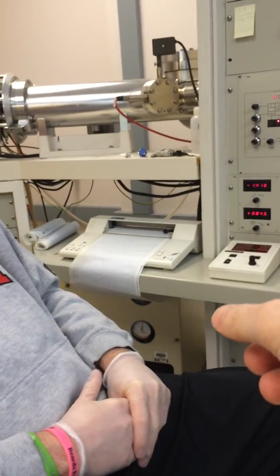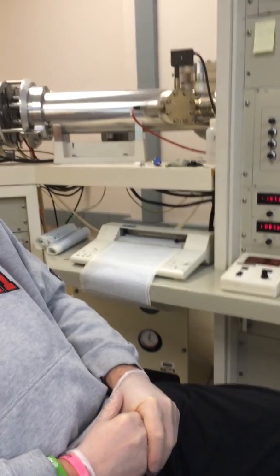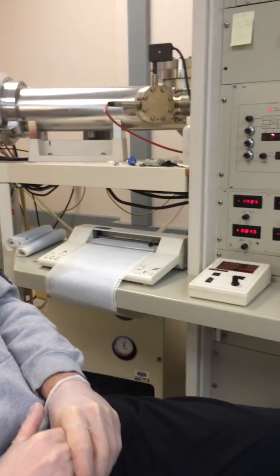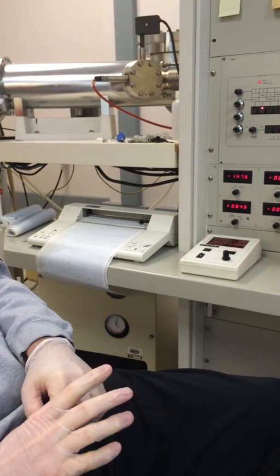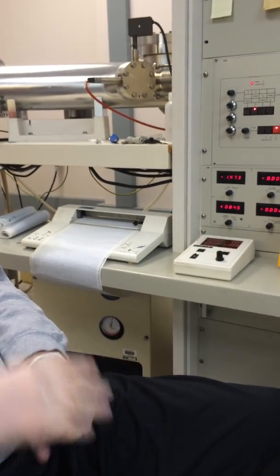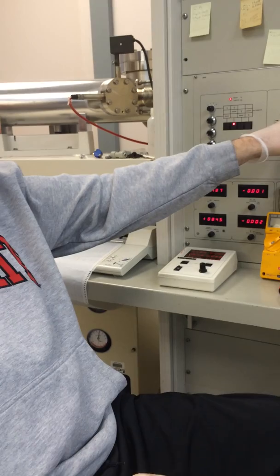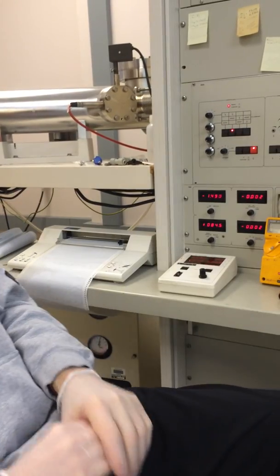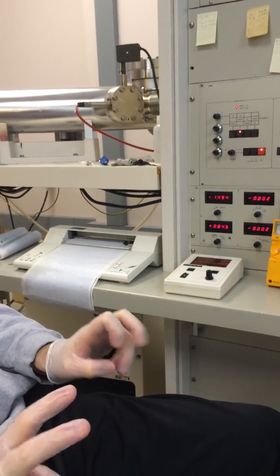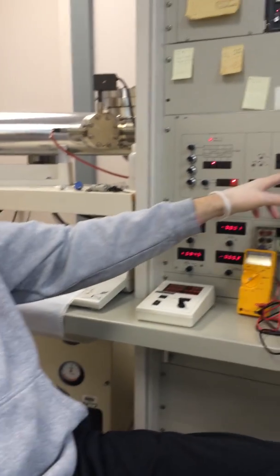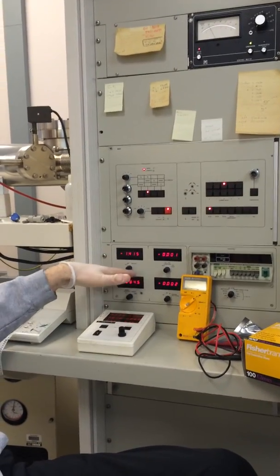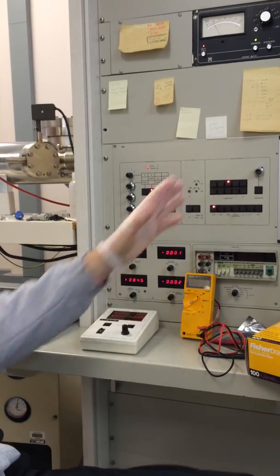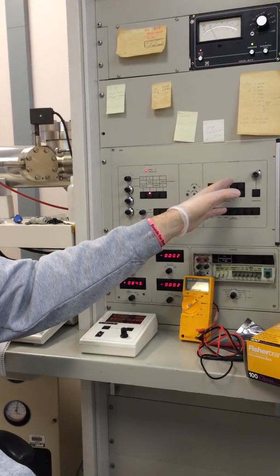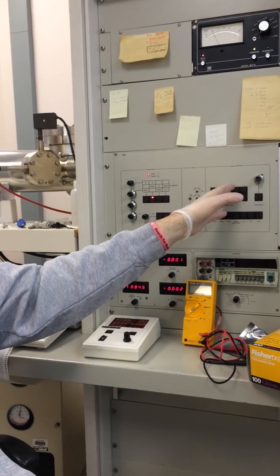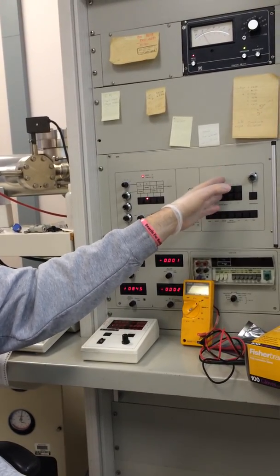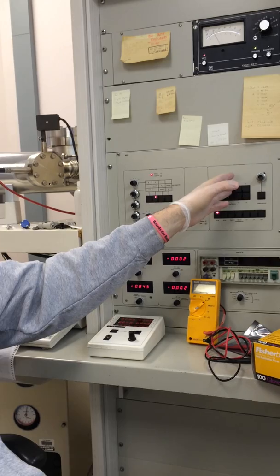So I mean, I see the mass, but how do you know which cup? I told it to put it in cup 3. So I said input channel 3, input mass 88. Okay. So when we're doing the reference calibration, everything is done off of cup 3 for this line. When we're doing neodymium, the reference cup is 6, so we calibrate everything in cup 6. So it has to know, since this is our reference cup, where to set the magnet so that mass 88, 87, 86, 85, 84 are in cup 3.